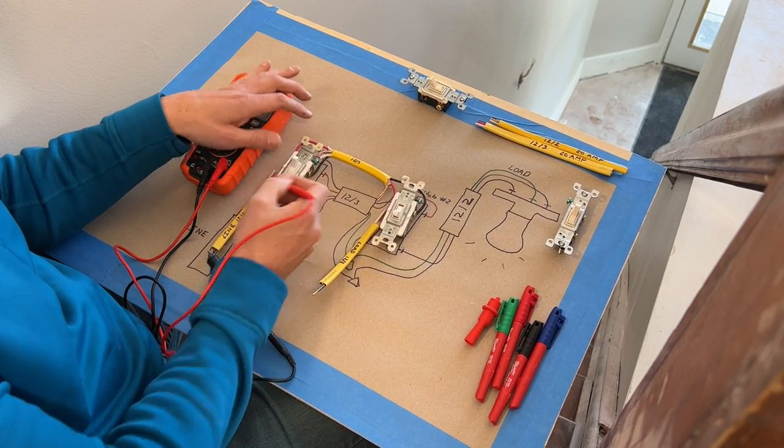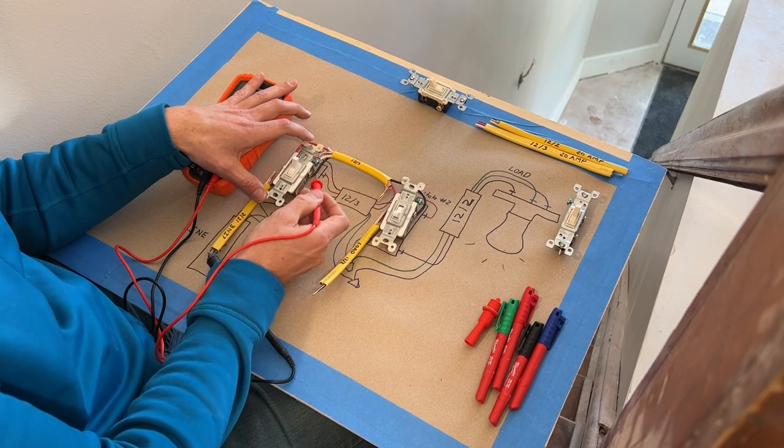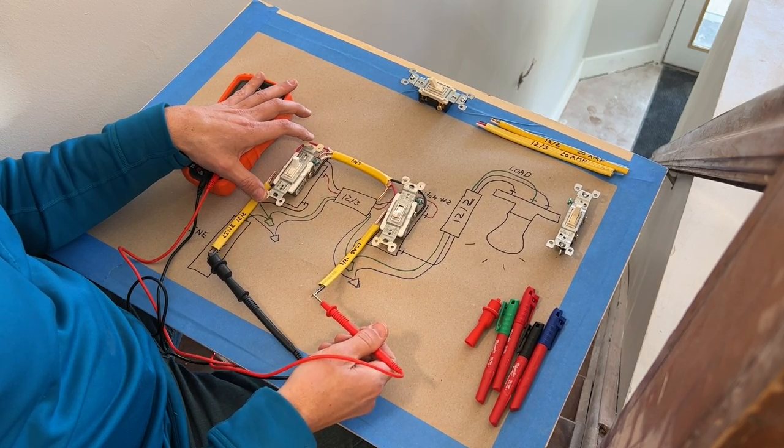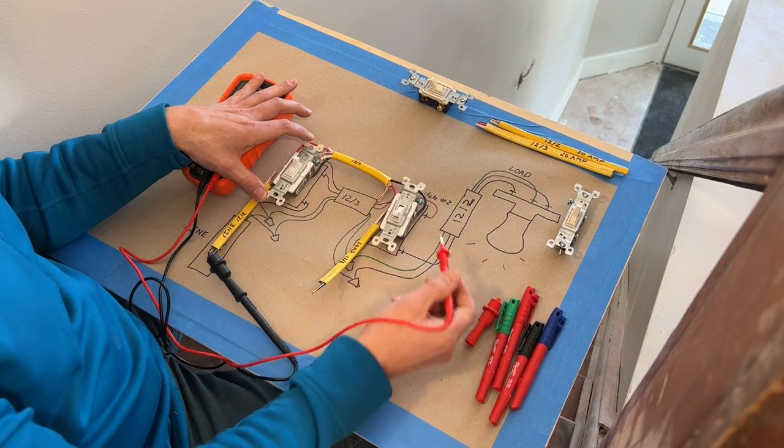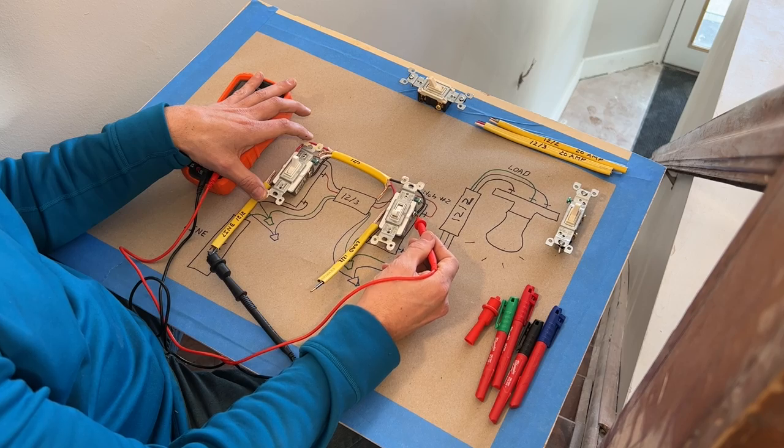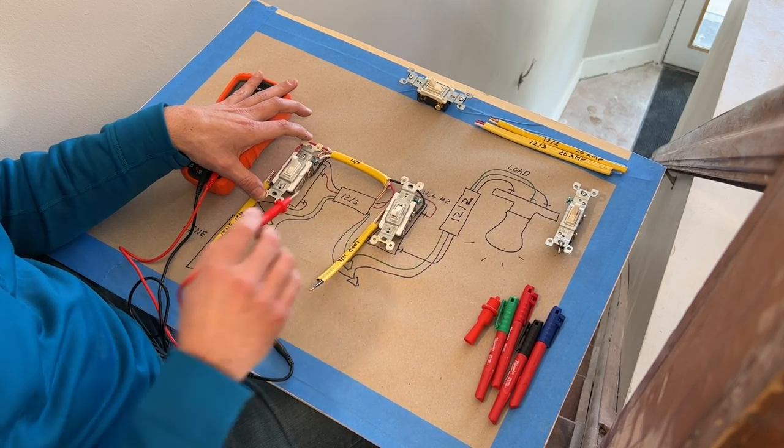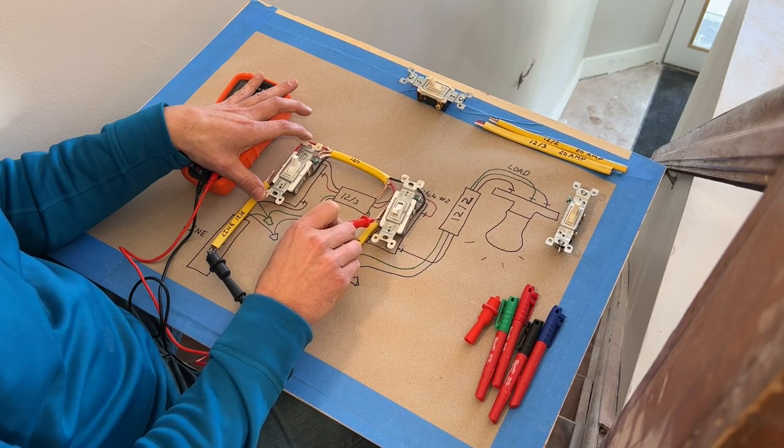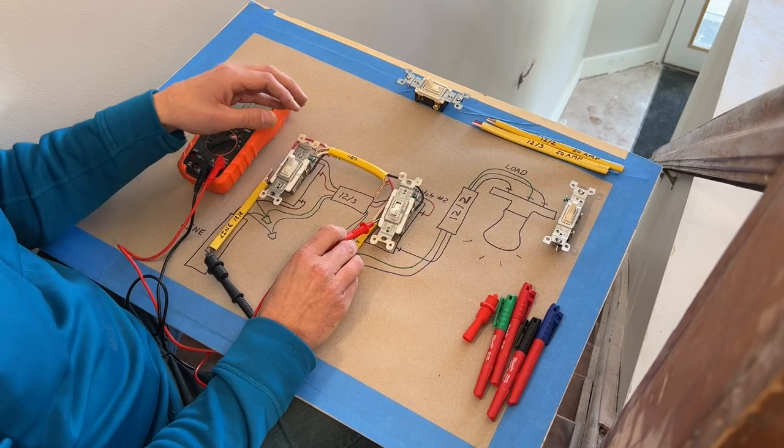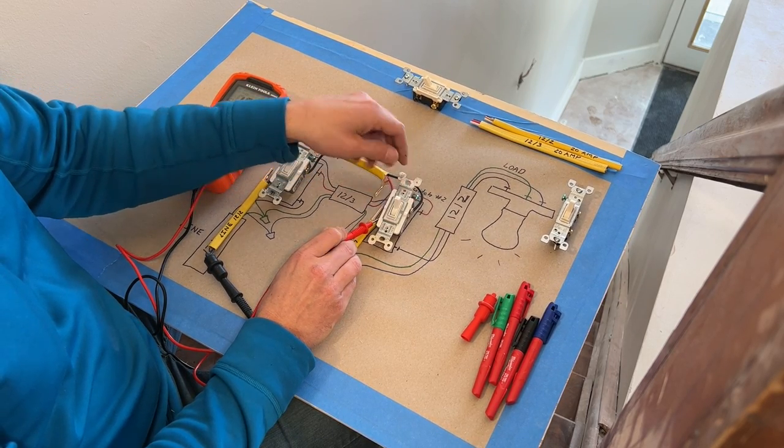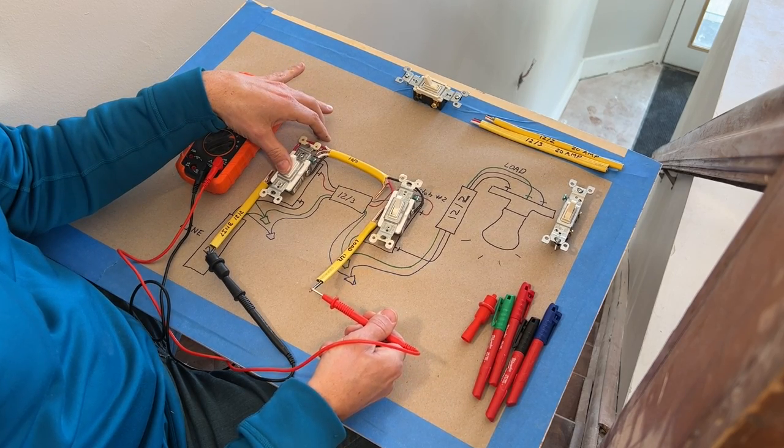So right now I have continuity through this light switch to this screw terminal. I do not have continuity all the way to my light. So if I follow the black through, we still have continuity, but then I go to the black terminal which would provide a connection to my light, I do not. I do not have continuity. Now if I test right there and I flip the switch, now I have a connection through, and I'd have a connection all the way through to my light switch.